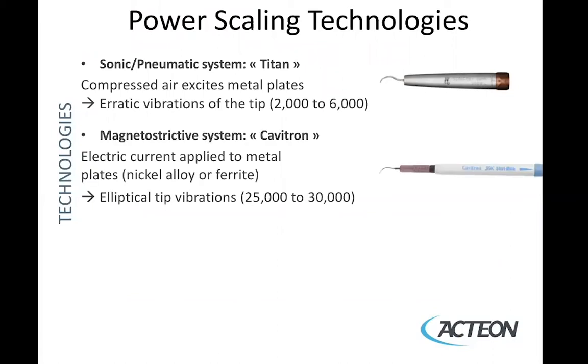In the category of ultrasonics would be magnetostrictive — an example is the Cavitron, where electrical current is applied to the ferromagnetic stacks creating an elliptical tip vibration of 25,000 to 30,000 times per second.